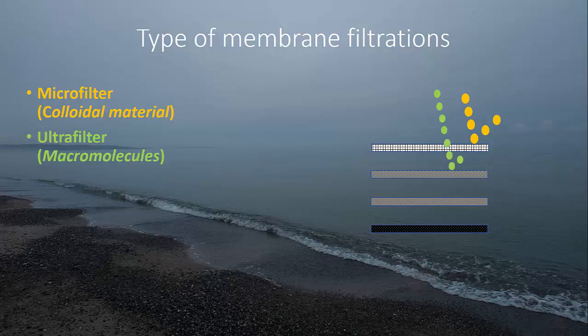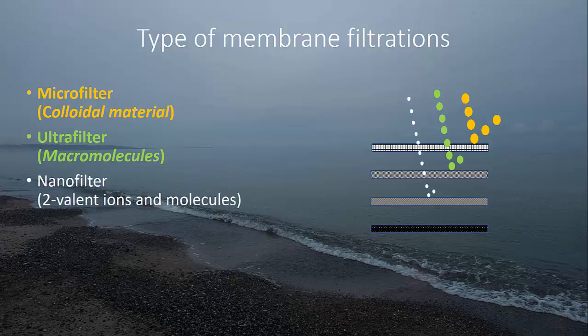The next step is ultrafilters, which can remove macromolecules. An ultrafilter is used for sewage treatment in membrane bioreactors, or MBRs. With an ultrafilter in an MBR you can remove very small things such as viruses and bacteria. Ultrafilters are also very importantly used as a pretreatment step for the next two types of membranes: nanofilters and reverse osmosis.